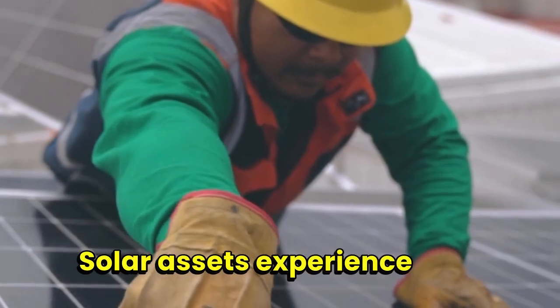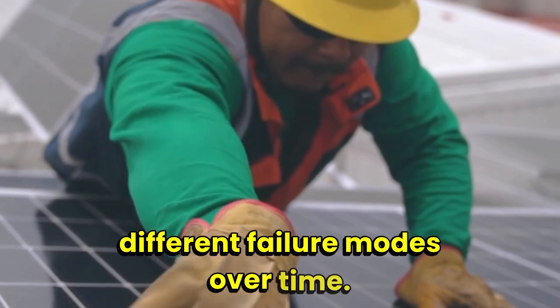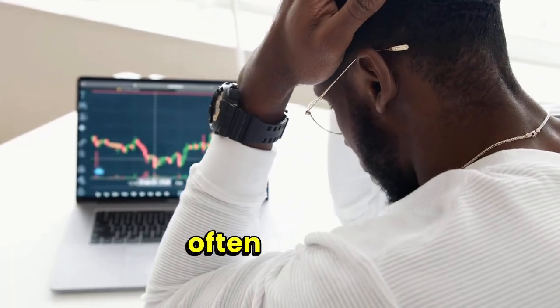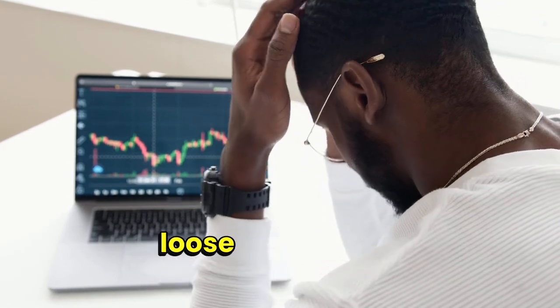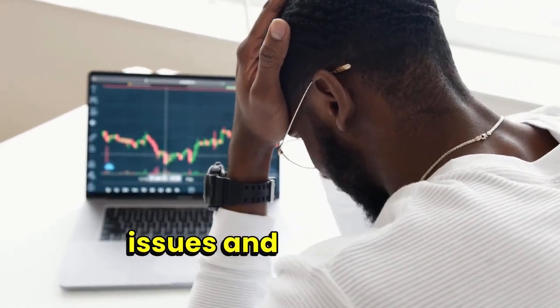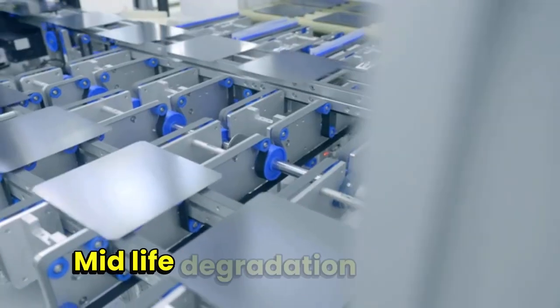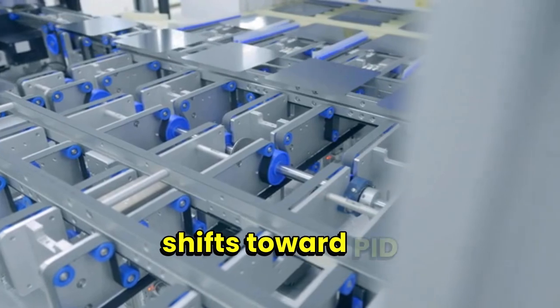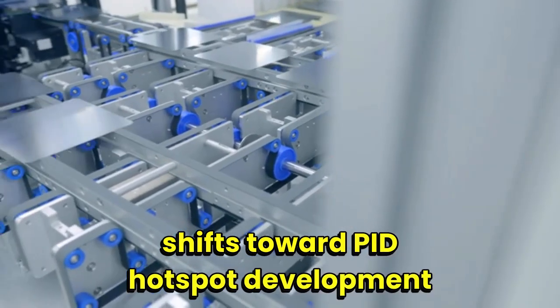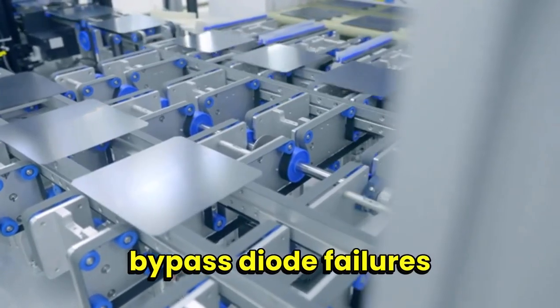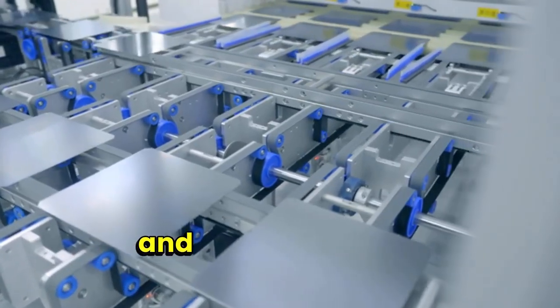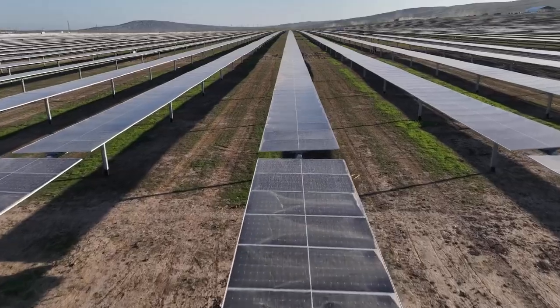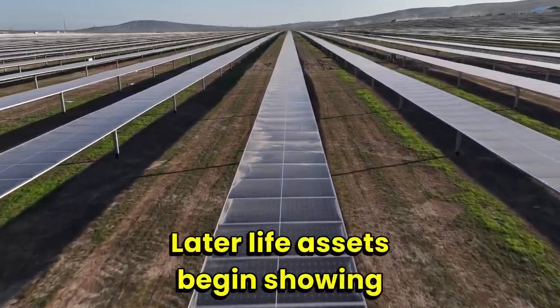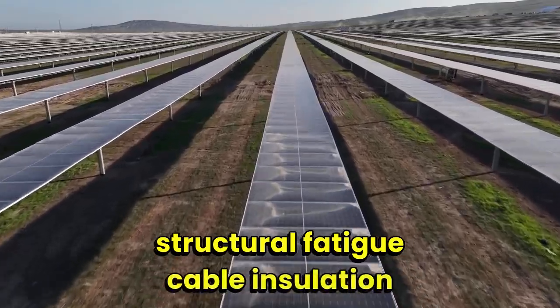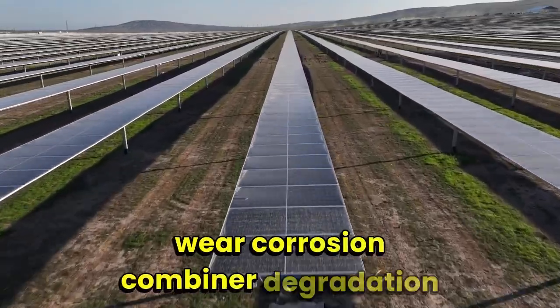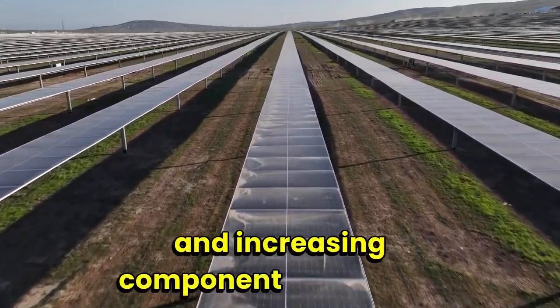Solar assets experience very different failure modes over time. Early life failures often include installation defects, loose connectors, commissioning issues, and grounding problems. Mid-life degradation typically shifts toward PID, hotspot development, bypass diode failures, tracker synchronization drift, and inverter cooling degradation. Later life assets begin showing structural fatigue, cable insulation wear, corrosion, combiner degradation, and increasing component mismatch.